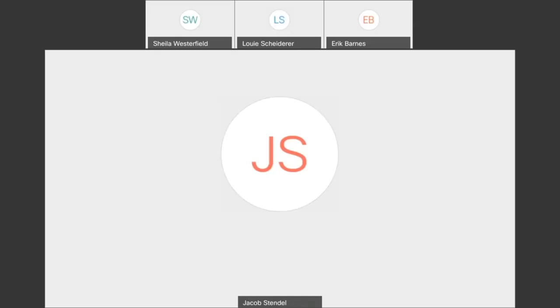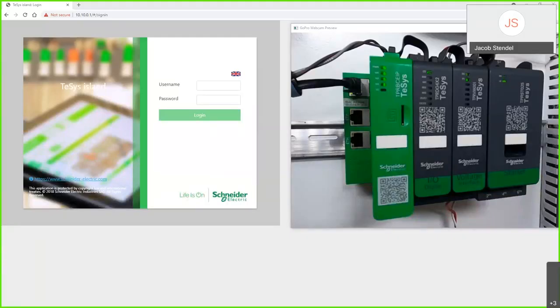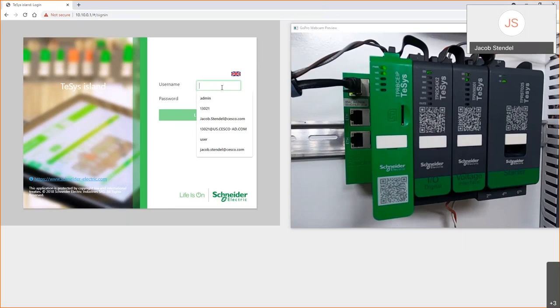I'm going to begin here by sharing my screen, and you should be able to see the live view of my TeSys Island setup and login portal to access the OMT tool. Essentially here, I have a bus coupler hooked up, a digital IO unit, a voltage interface, and a starter. Eric covered a lot of the main points on it. You can have up to 20 modules on an island, plus the bus coupler and the voltage interface module. This unit here is a basic one direction starter. There are options for reversing, two speed, conveyors, pumps, Y delta, and so on.